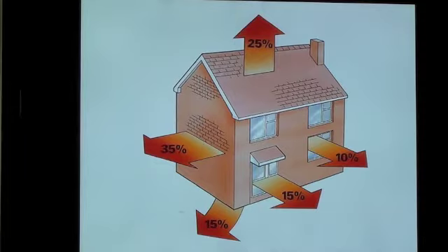So wherever the insulation is, we usually have a reasonable insulation amount. However, wherever there's structural members, there's not much insulation there because the structural members are conductors, not insulators. And so you get accelerated heat loss wherever there are structural members. We call that thermal bridging. So a 2x6 R20 wall really doesn't perform like an R20, it's more like an R15 to an R17 because of the thermal bridging, okay?